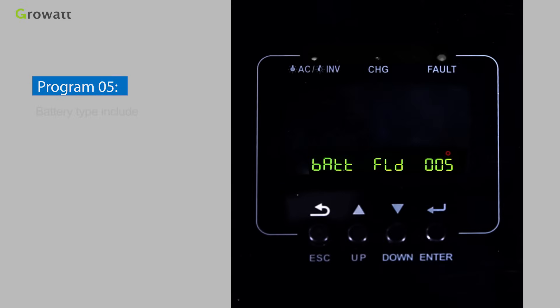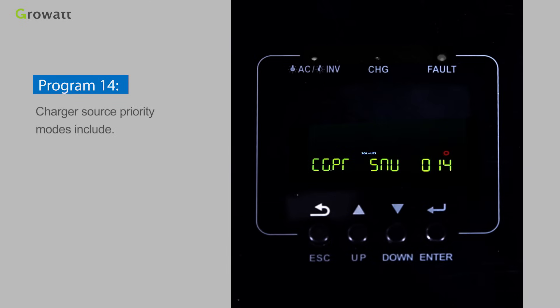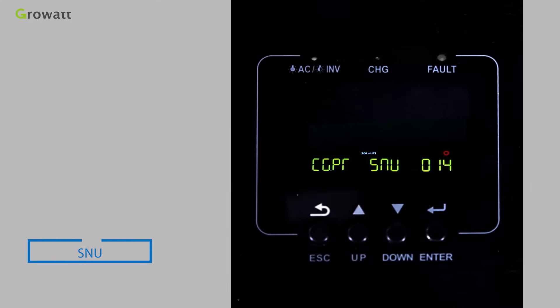Program 05 sets the battery type, with options including AGM, FLD, USE, Lithium, and USE2. If connecting a lithium battery, check the lithium battery compatibility list and set the relevant battery type and communication protocol. Program 14 sets the charger source priority with modes: CSO (Solar first), CUE (Grid first), SNU (Solar and Grid), and OSO (Only Solar). Note: when the inverter is working in line, standby, or fault mode, the charger source can be programmed.